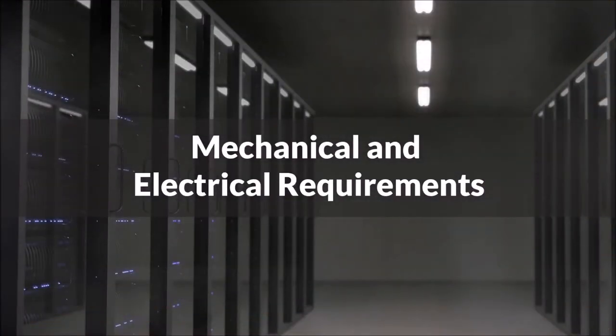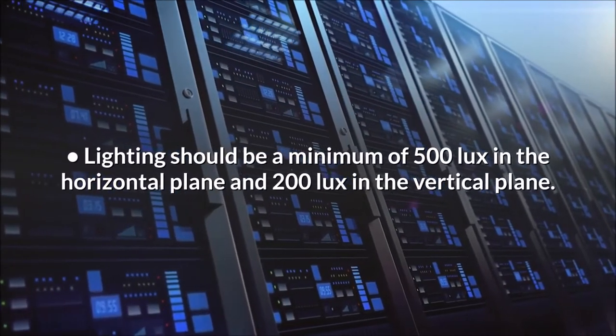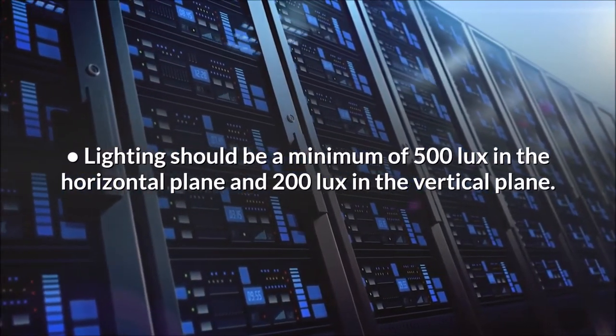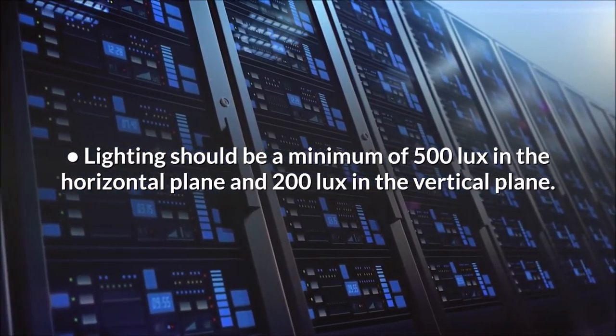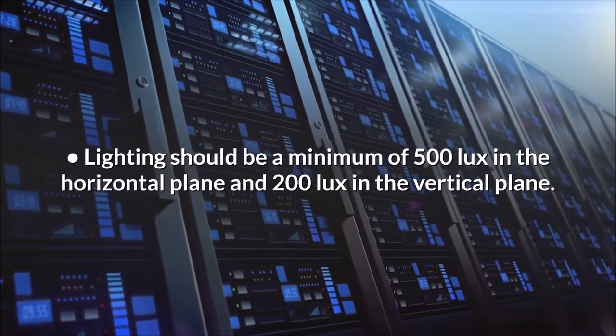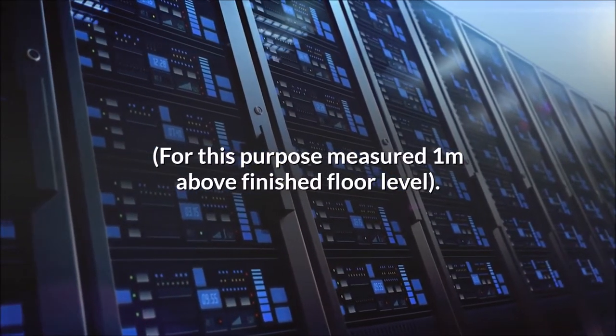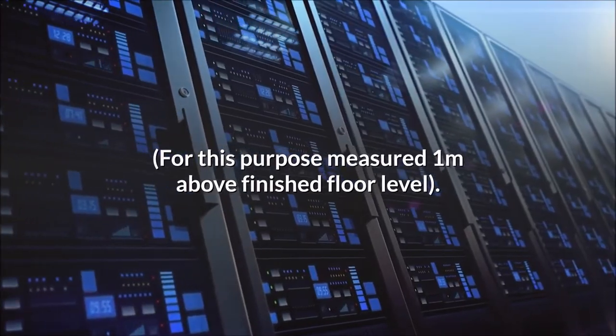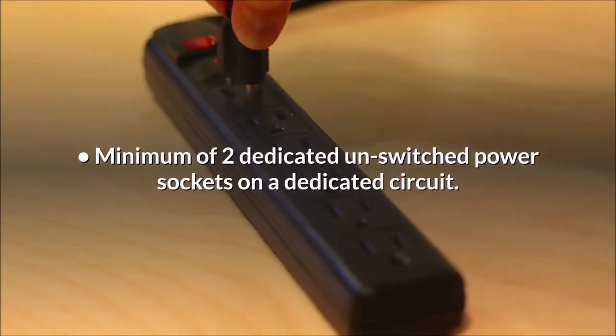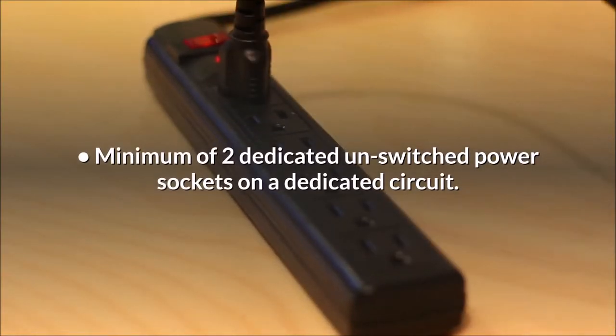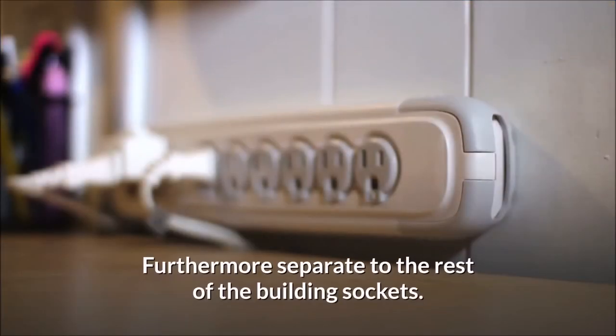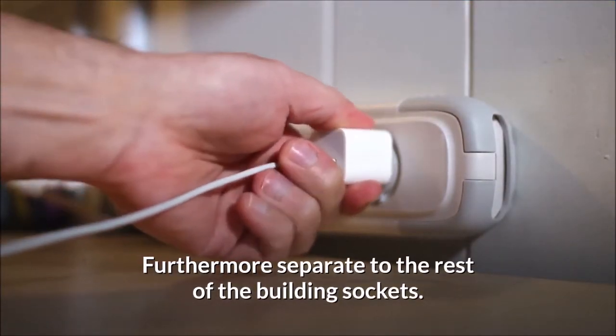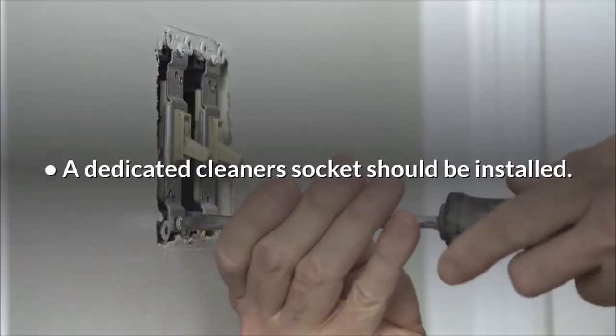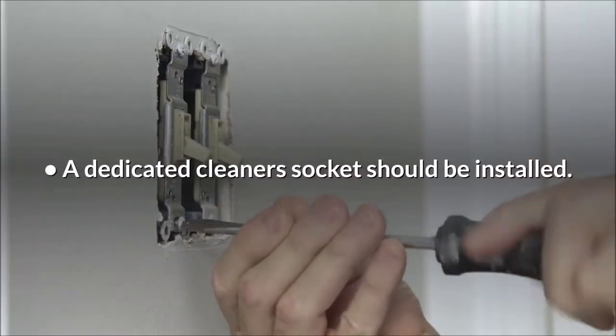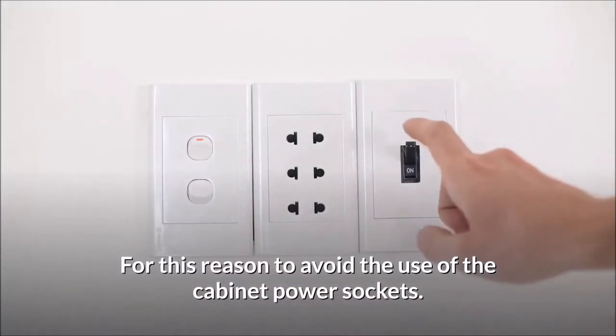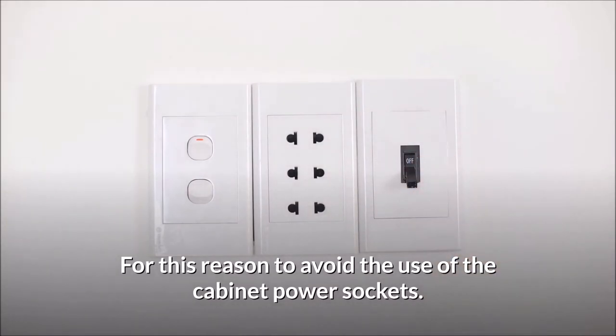Mechanical and electrical requirements. Lighting should be a minimum of 500 lux in the horizontal plane and 200 lux in the vertical plane. For this purpose, measured 1 meter above finished floor level. Minimum of 2 dedicated unswitched power sockets on a dedicated circuit. Furthermore, separate to the rest of the building sockets. A dedicated cleaner's socket should be installed. For this reason, to avoid the use of the cabinet power sockets.